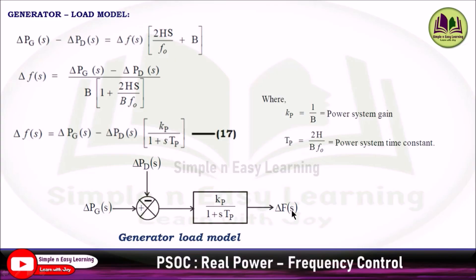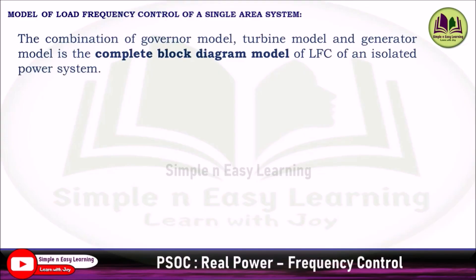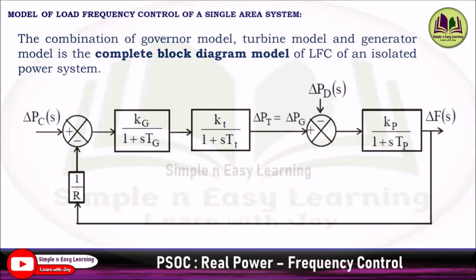We have now discussed the speed governor model, the turbine model, and the generator-load model. Combining all three gives the complete block diagram known as the Load Frequency Control (LFC) of a single area system. The input is del_Pc (speed changer input), followed by the governor block Kg/(1+s·Tg), then the turbine block, then the generator-load model. This is the complete block diagram model of LFC of an isolated power system.